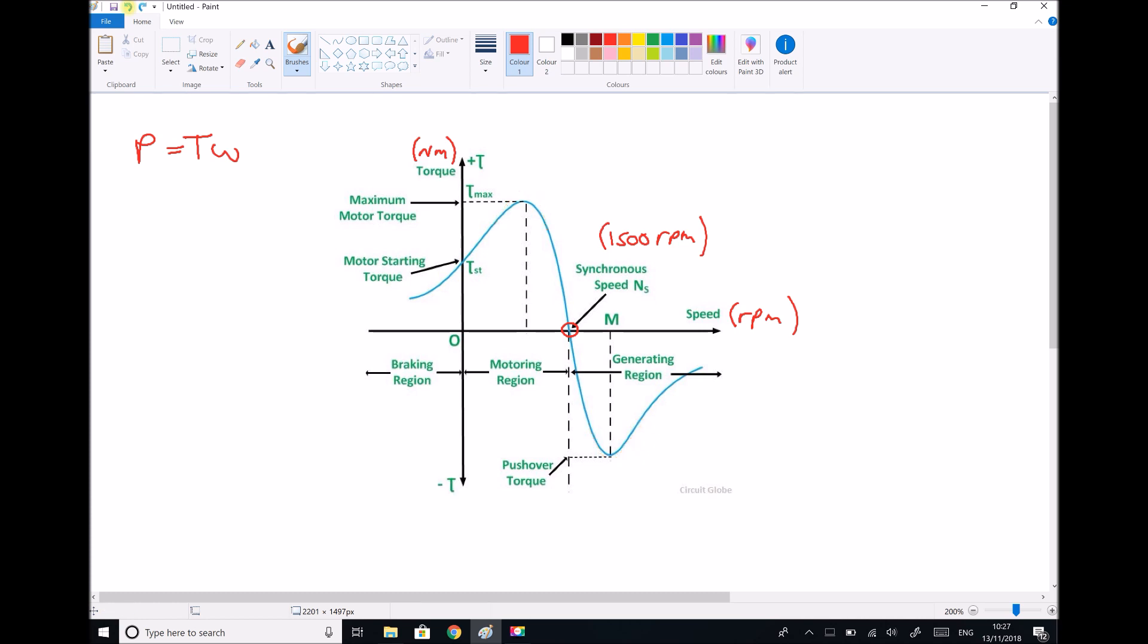What is this diagram actually showing? Left of the synchronous speed, or speeds below 1500 RPM, we can see that we're producing torque. We have a positive torque. In order to produce torque we would need to draw power. The machine is essentially motoring. It's drawing power to create torque.